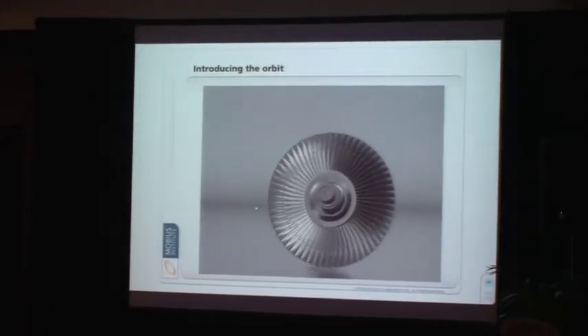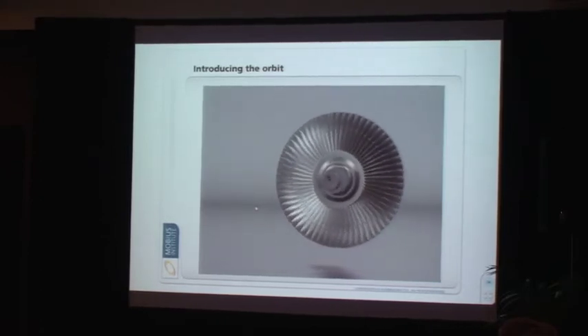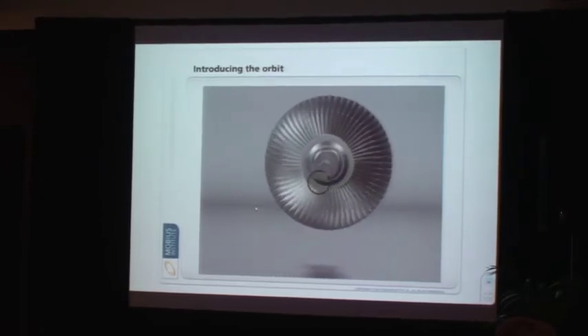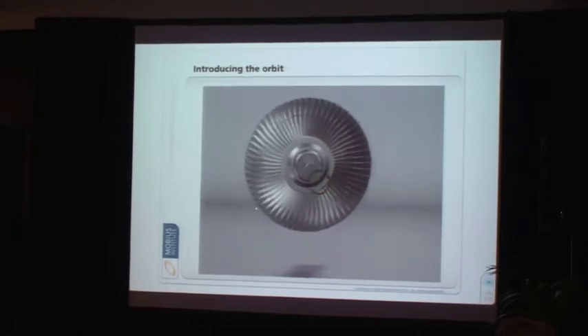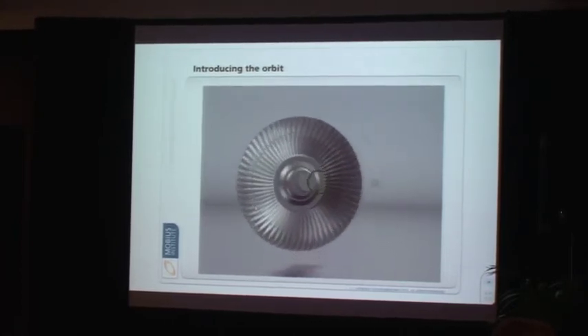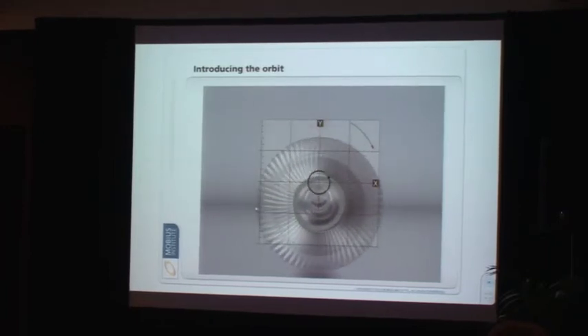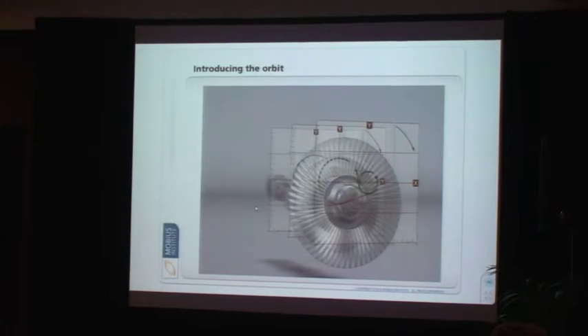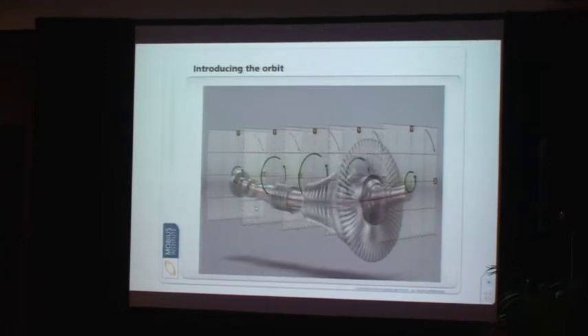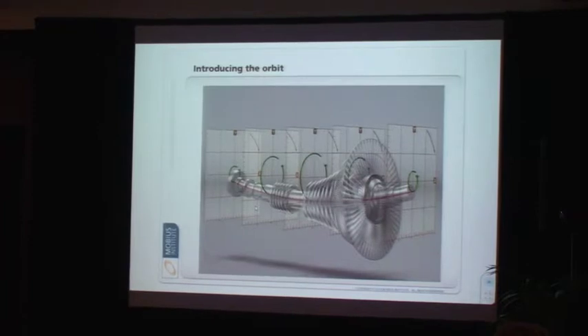What we really want to do is say, what is that shaft doing? We've got our two probes watching it carefully. What we're really interested in is, what is the center of that shaft doing? In this case, you can see it's moving in a circular motion, and that's exactly what the orbit is telling us. Now, we might be measuring the outside of the shaft, but it's round, so we can project in our minds back to the center of the rotor. So if the rotor is moving in a circular motion, and we compare those two signals from the X and Y probe, we get a round orbit in that case. And that's exactly where this comes from.